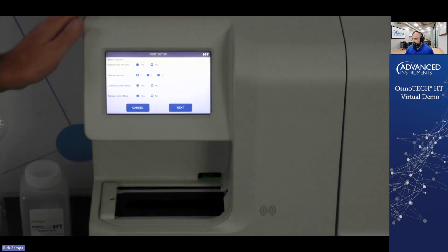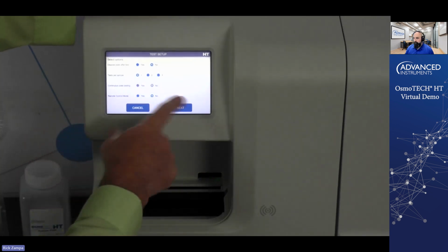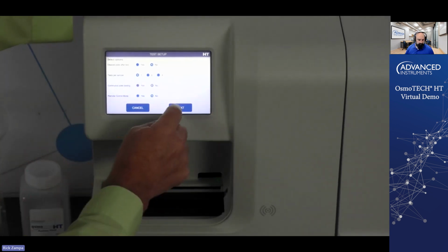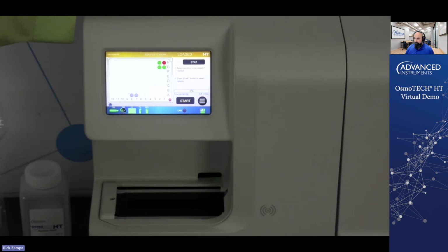Continuous plate testing would be if I were going to load on 2 plates. So I load the first plate in, then I put the second plate on, which allows you to run 2 full plates, which is about 6.5 hours of testing. So you could put those in, walk away in the evening, and let it run all night. And remote control, I'm not remote controlling it. I'm doing everything here locally. Then I'm going to hit next.